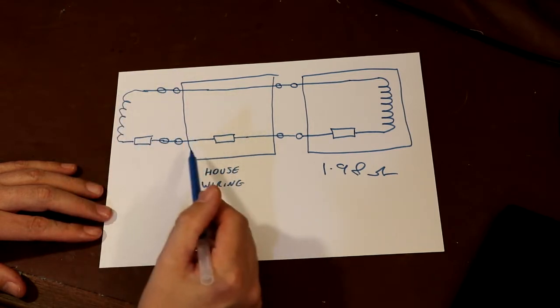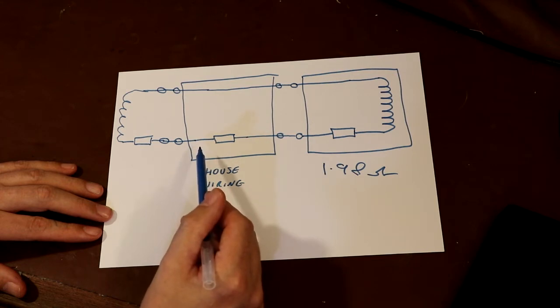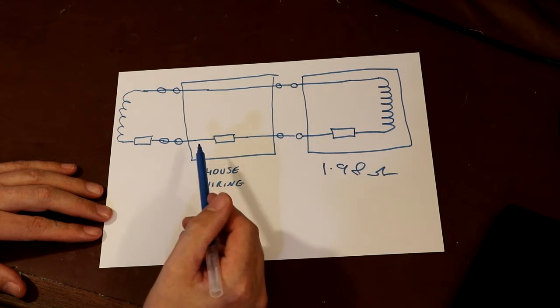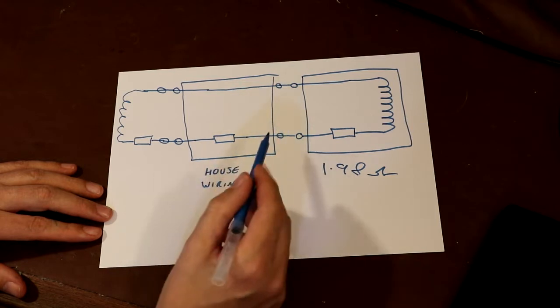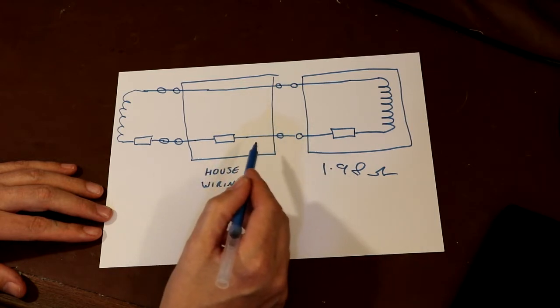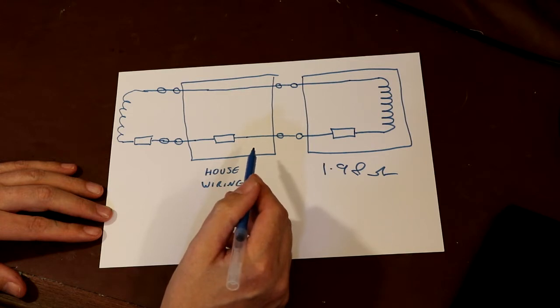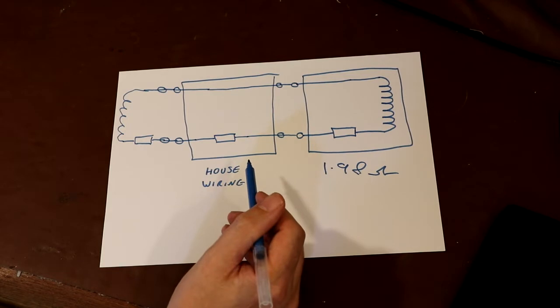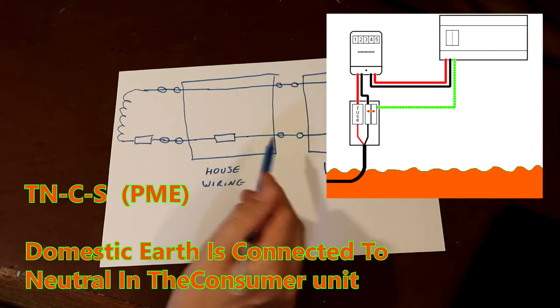Well, I'm going to use a special function on this Fluke meter to measure something called Z-loop. Now, I'm not particularly familiar, I'm not an electrician, but I think the Z-loop reading is between the earth and the live conductor. But because of the type of electrical installation that I've got in my house, which is PME, my earth wire and my neutral conductor are effectively the same thing. So I'm going to try to use this Fluke meter to measure the impedance of my supply here.